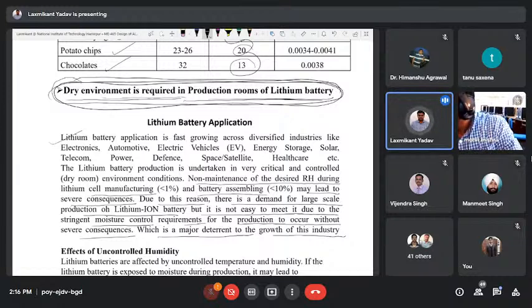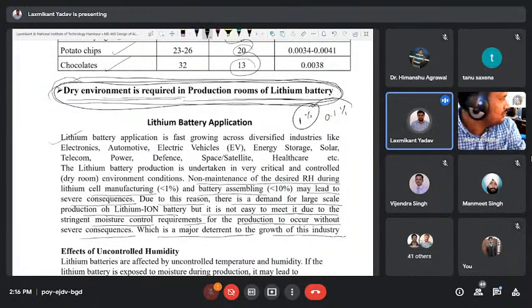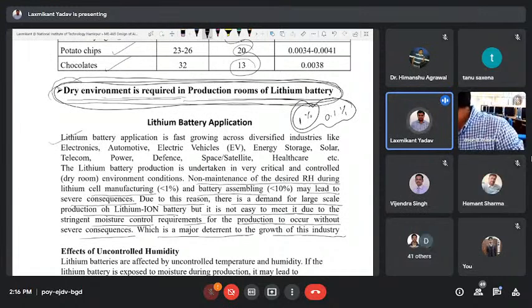So in a lithium ion battery production room, we require a relative humidity of less than 1%, even 0.1%, and this type of strict relative humidity can only be controlled by the use of the desiccant wheel. Okay, not with the help of a conventional system or liquid desiccant system. So this type of relative humidity requirement we can easily achieve with the help of the desiccant wheel. That's why this desiccant wheel is commercially successful.